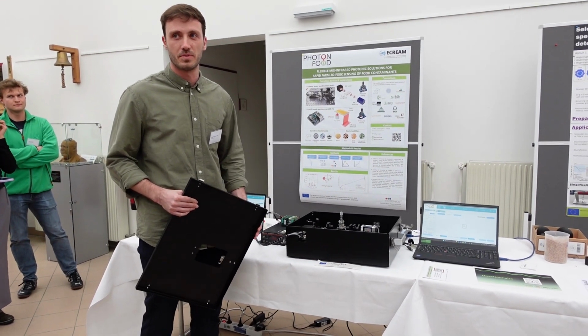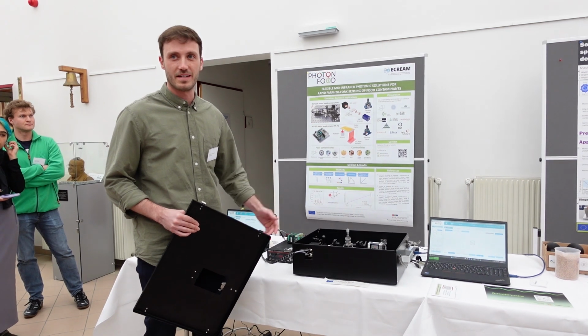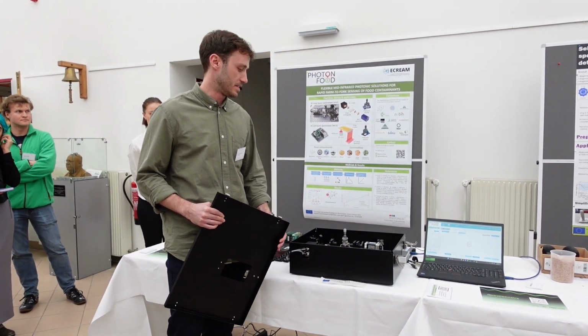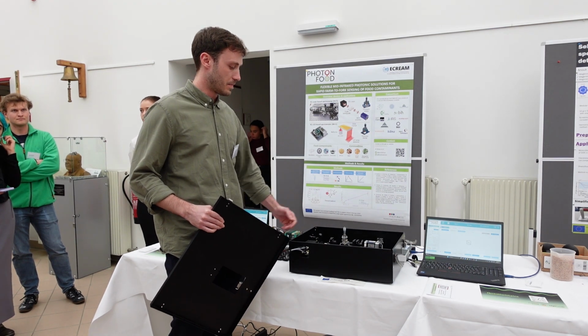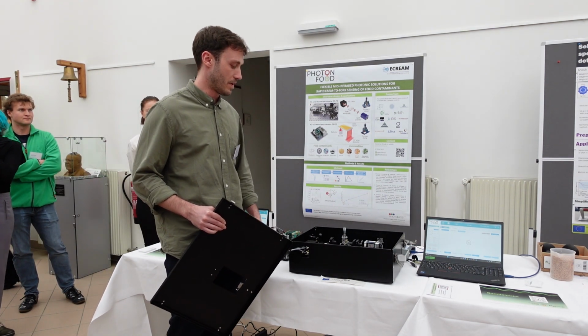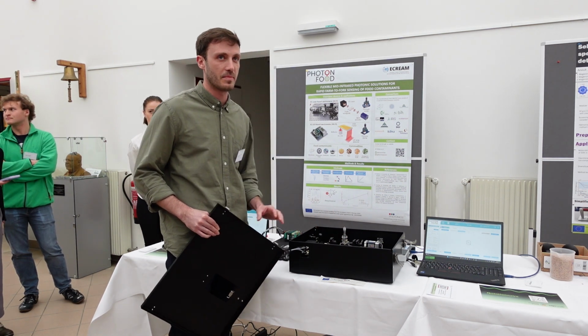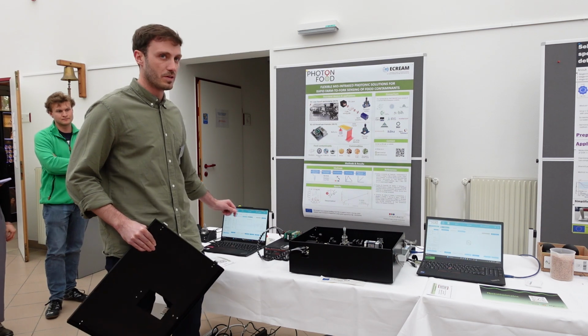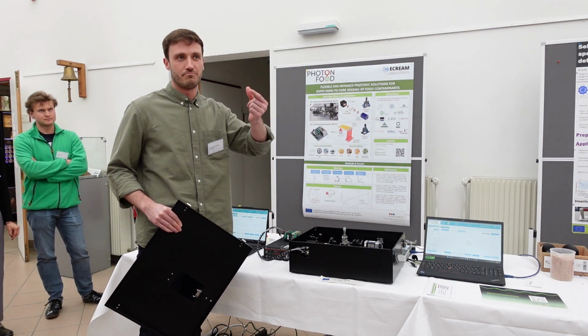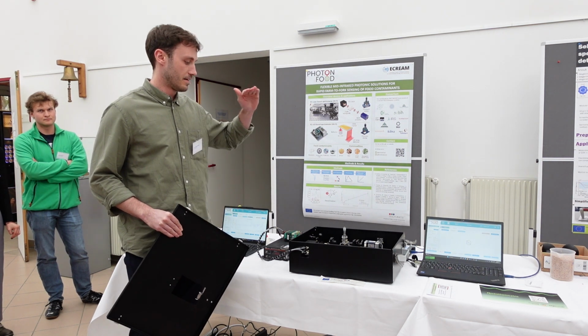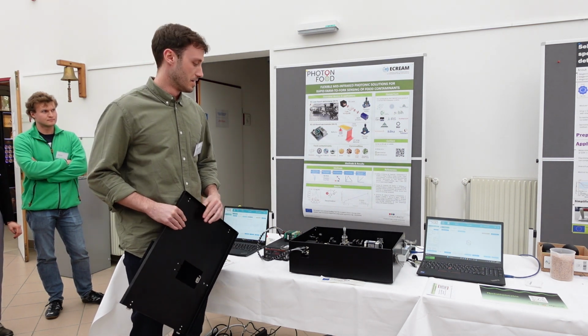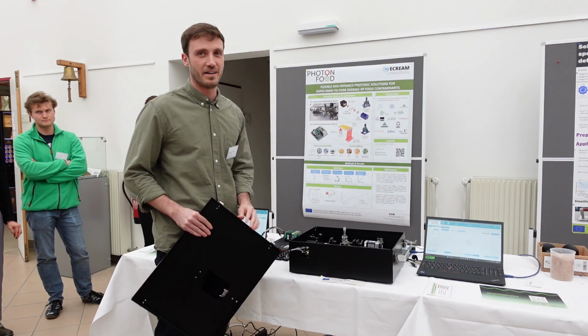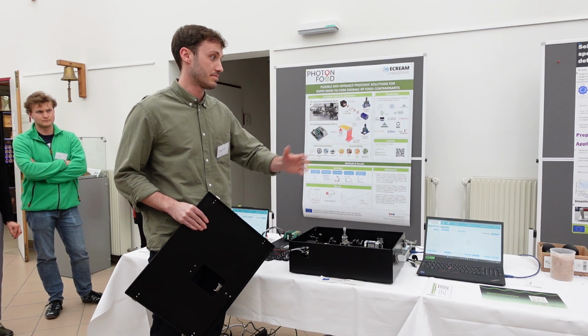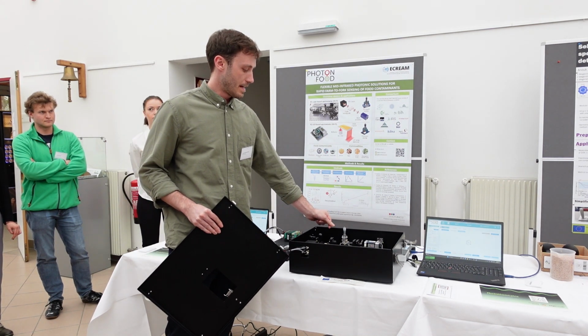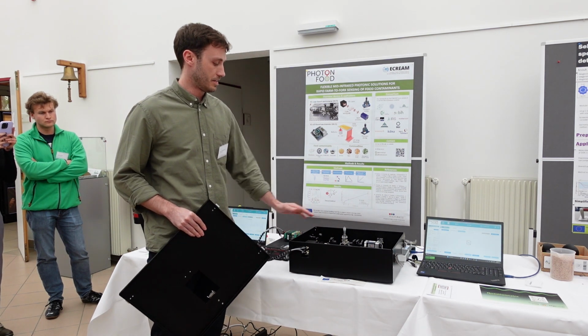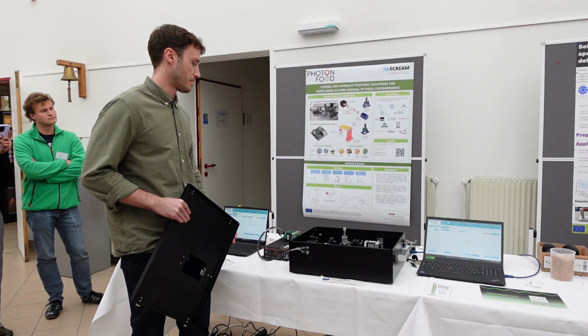this new laser developed in the PHOTONFOOD project allows us to miniaturize the device and to have a really compact optical system. As you can see here, it just consists of two different mirrors which focus the light onto the waveguide. This is also the sensing element, and the waveguide in this case is smaller than for the MiFi. It's just a 10 by 5 millimeter waveguide and 6 microns in thickness. So in this case, the paper, which would interface with the sample preparation from Anouk, can be even smaller, and it's just placing the paper tip here on the sensing element and recording the measurement.